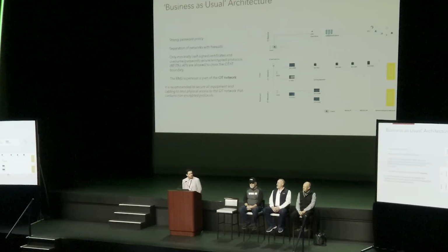Well, with the setup, I guess, are you sure? I think the first thing I'd say is, one, you'd have to get comfortable with IP, right? So if you haven't really done any BACnet IP jobs or understanding the Ethernet network, you need to go through that first. Aside from that, the next thing for BACnet SC is deciding who that issuer or that local certificate authority owner is going to be, right? Is it the customer's IT department? Is it going to be you as the system integrator?